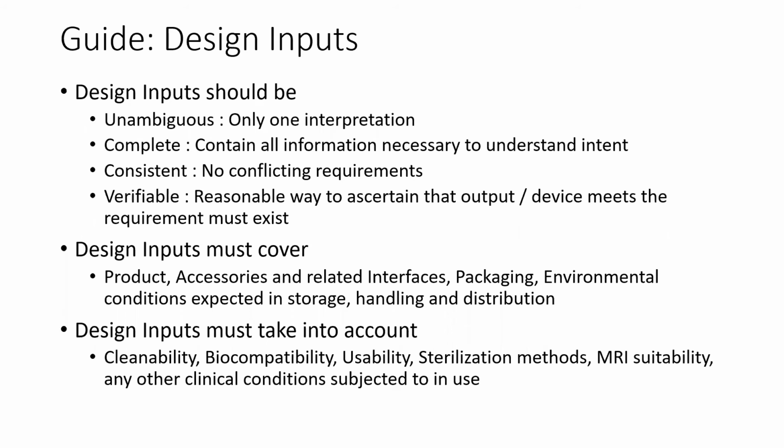So it's not enough for design inputs to only speak about the core of the device or the clinical aspect or the function. Okay, accessories to the device, interfaces, packaging, the clinical conditions that a device has to meet while in service, the environmental conditions expected in storage, handling, transit, distribution, all need to be covered in design inputs. So remember, you have to think product life cycle from the day it starts to the day it is disposed.